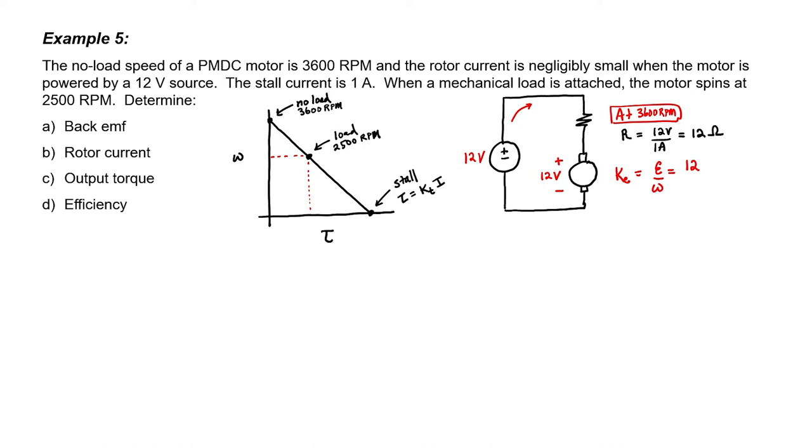It's not too difficult now to find the back EMF constant because I know both the back EMF and the speed. After converting 3600 rpms into radians per second, we end up with a value for the back EMF constant. I'm going to put a box around it because this is a constant that applies to every point along that line in the graph.